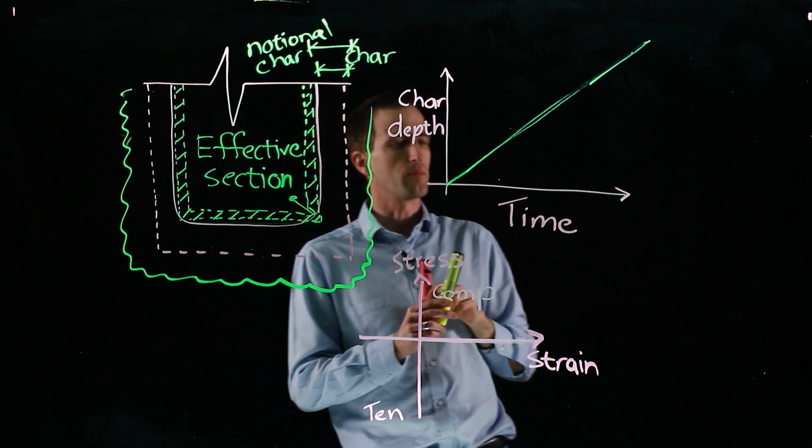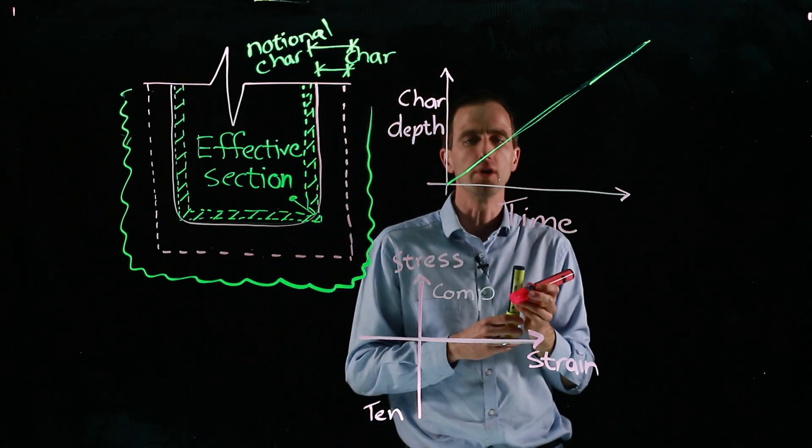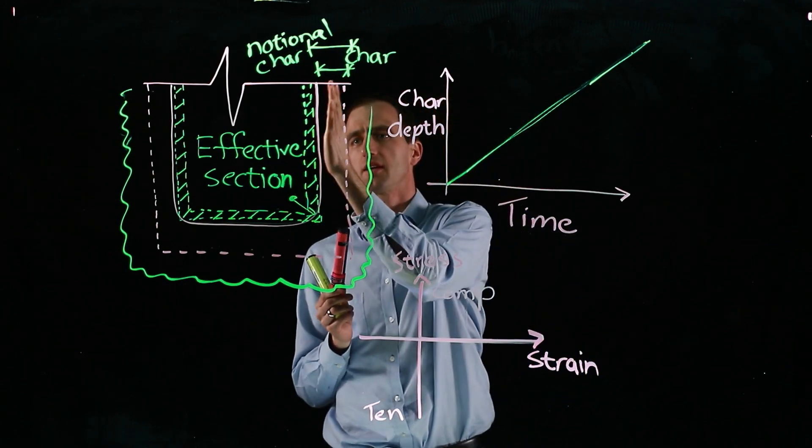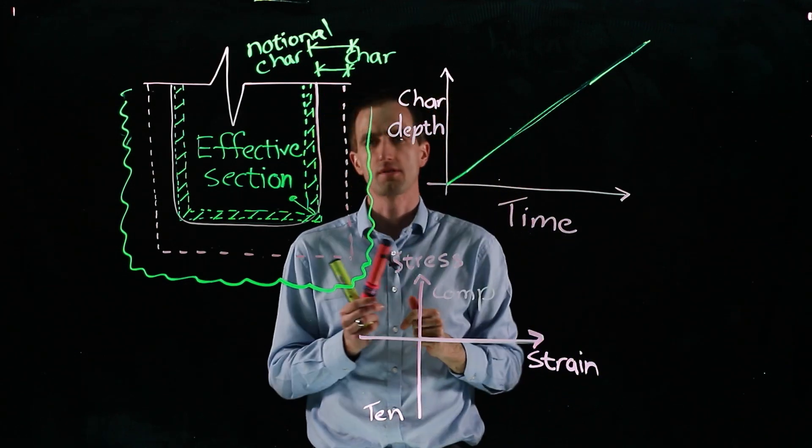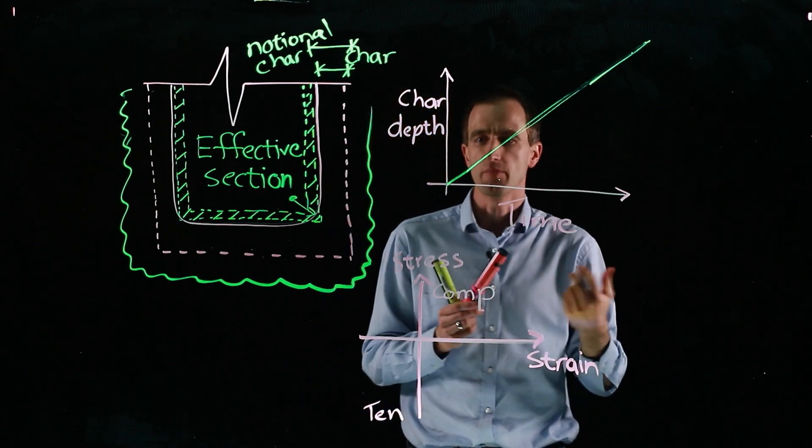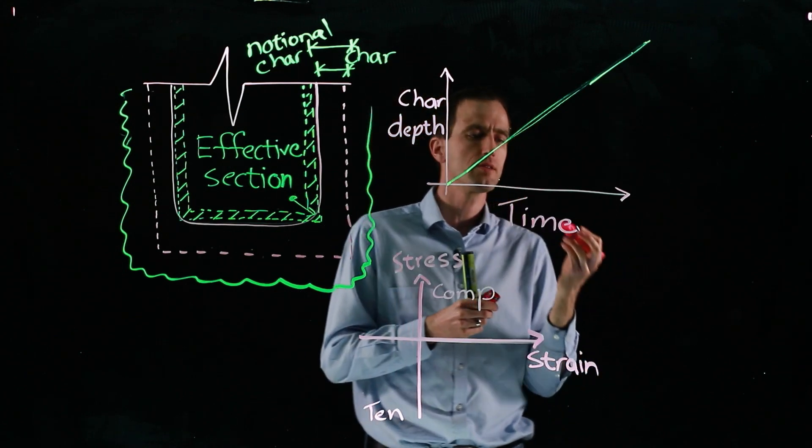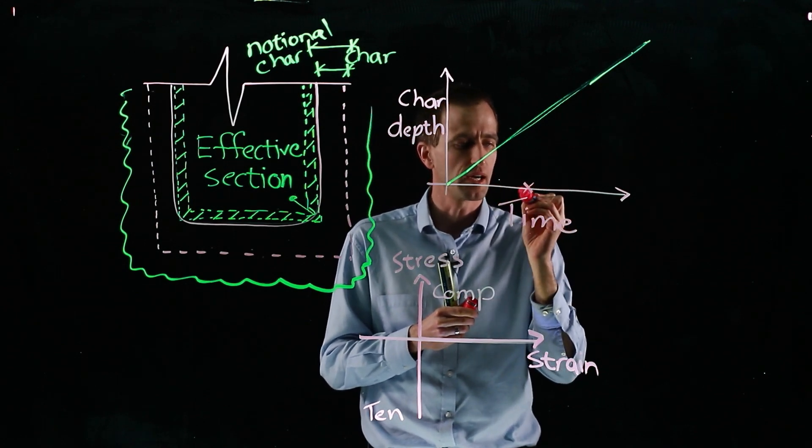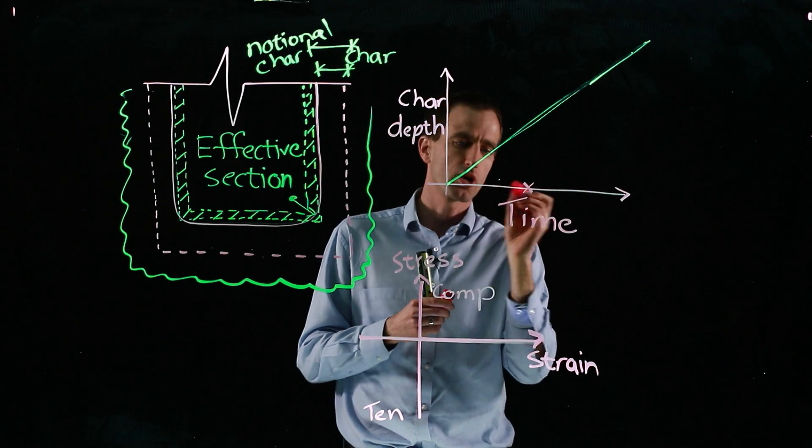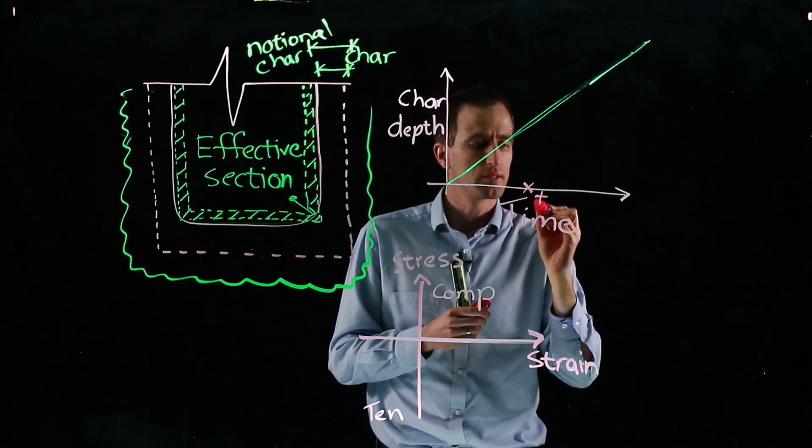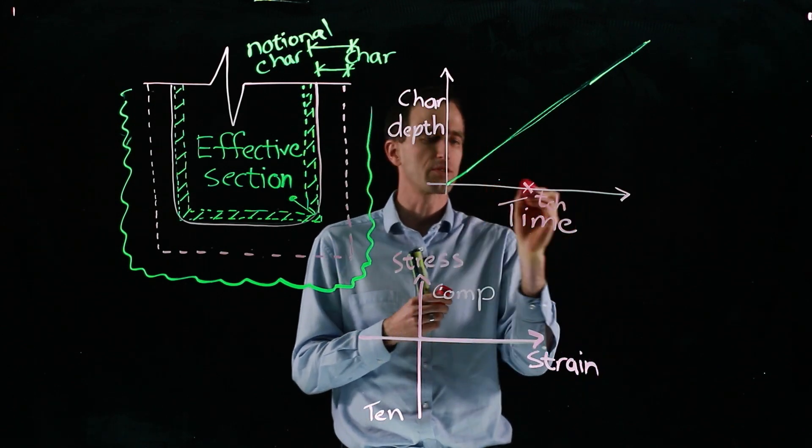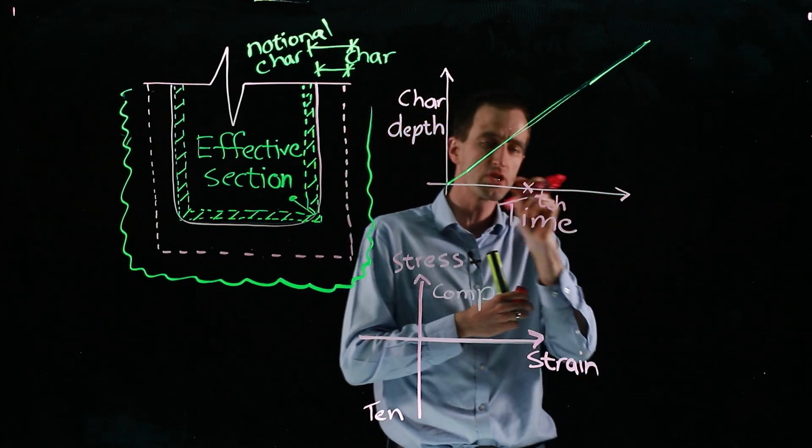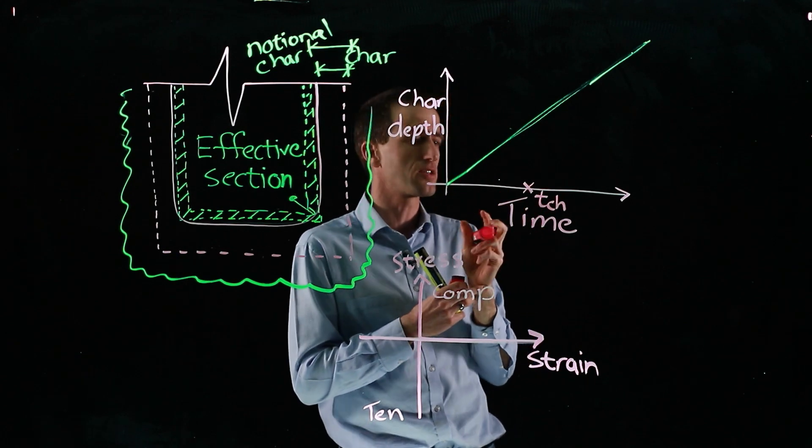But there are also other different models that exist. And for instance, let's say we had a protective layer, a board fixed onto the side of our timber, we want to get some extra fire rating out of it. There are other models, for instance, where you have after a period of time, there is no charring until the heat penetrates sufficiently through our protective layer, our gypsum board, Type X gypsum board or whatever it is. So now we have a time at which charring starts.